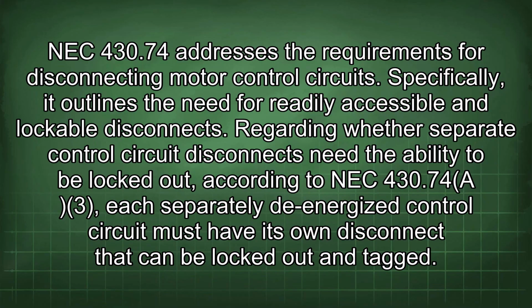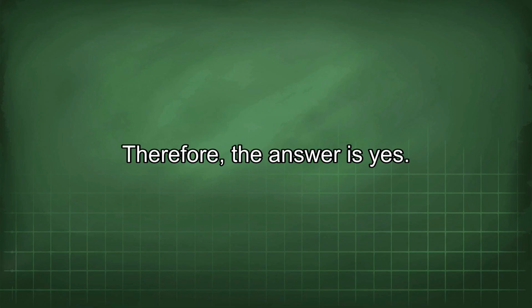NEC 430.74 addresses the requirements for disconnecting motor control circuits. Specifically, it outlines the need for readily accessible and lockable disconnects. Regarding whether separate control circuit disconnects need the ability to be locked out, according to NEC 430.74, each separately de-energized control circuit must have its own disconnect that can be locked out and tagged. Therefore, the answer is yes.